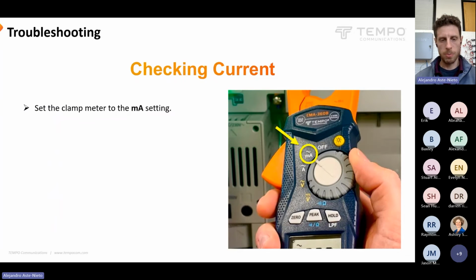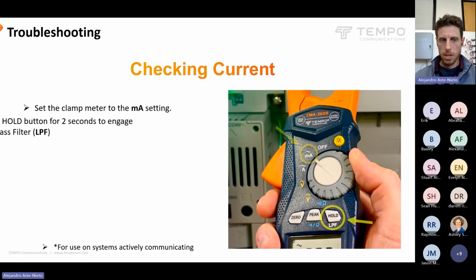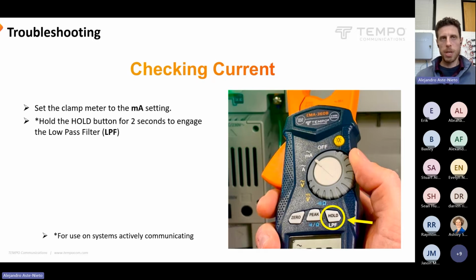So when it comes to checking current with the clamp meter, set it to the milliamps mode at that first setting with the rotation of the wheel. If you're taking these measurements when there's an idle system and that system is trying to communicate with decoders, and those bursts of communication are happening, it'll be helpful to engage the low pass filter. You just hold the button that says hold and LPF underneath it for 2 seconds. You'll see LPF appear on the screen down here, and it'll help to ignore those bursts of communication.